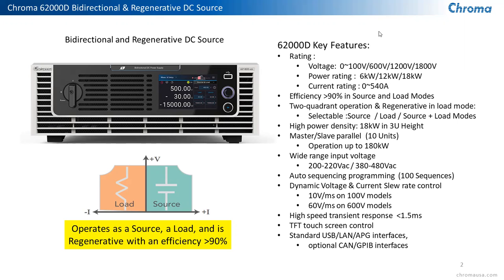We can parallel these up to 10 units to get you up to 180 kilowatts of total power, both as a load and as a source. Wide range input, 200 to 480 volts. It has a lot of additional features, auto sequencing. We also have software available that allows us to use this unit as a battery simulator. We'll get into that in a little more detail.